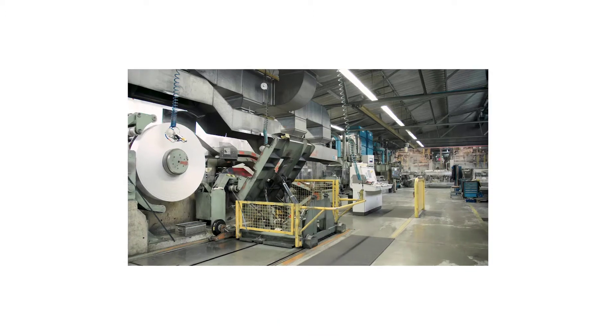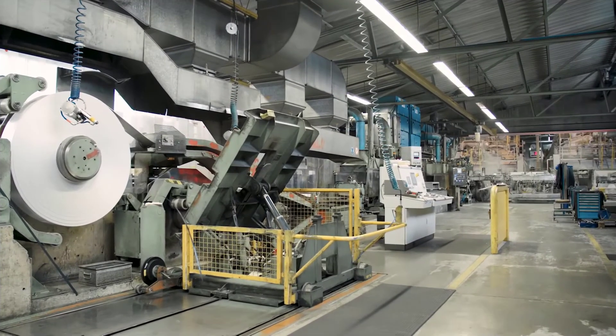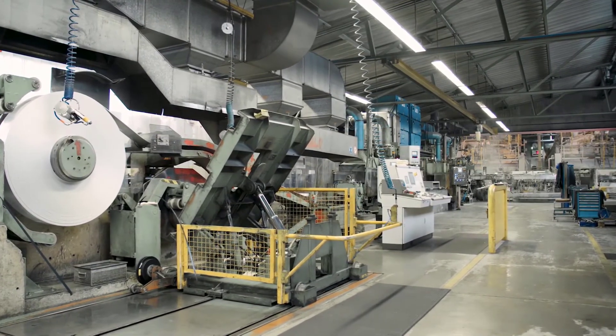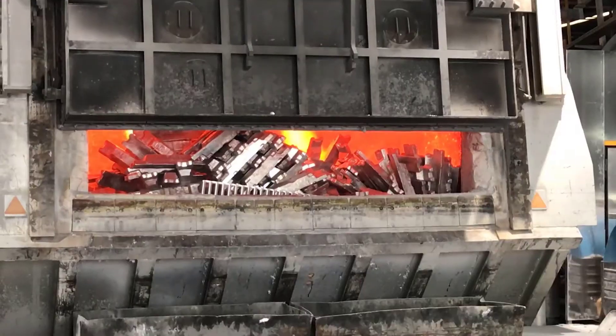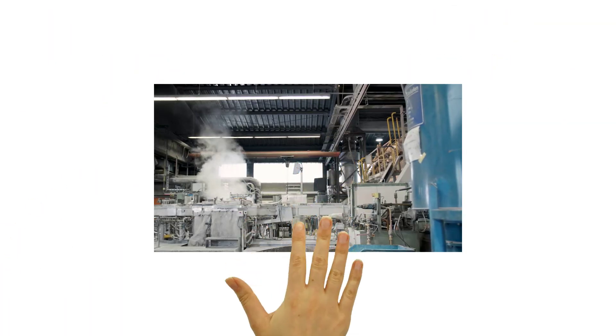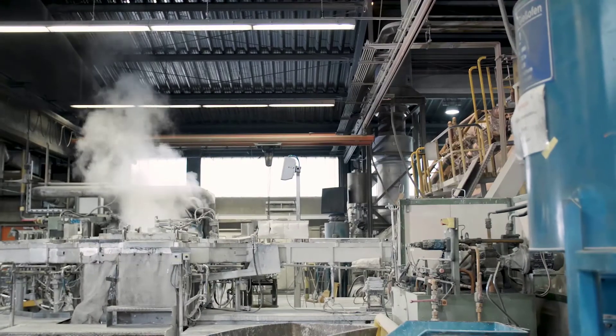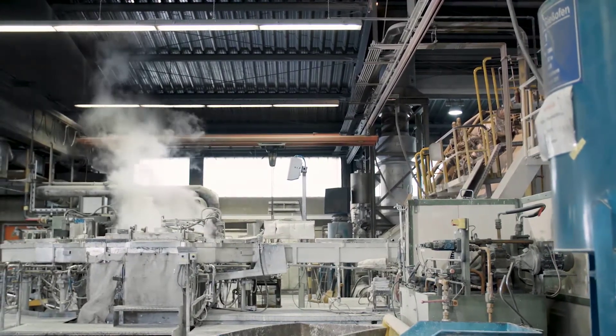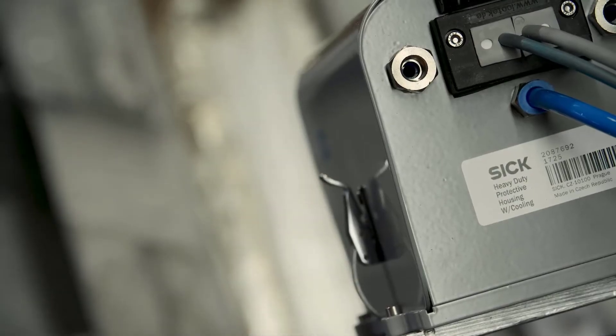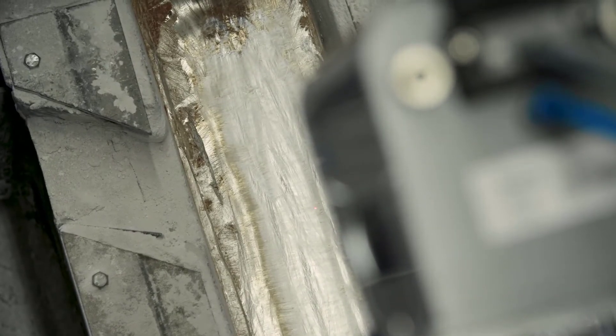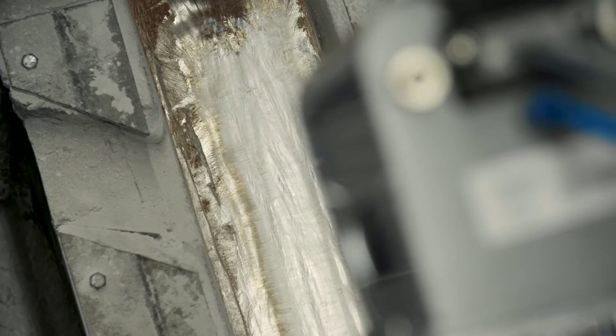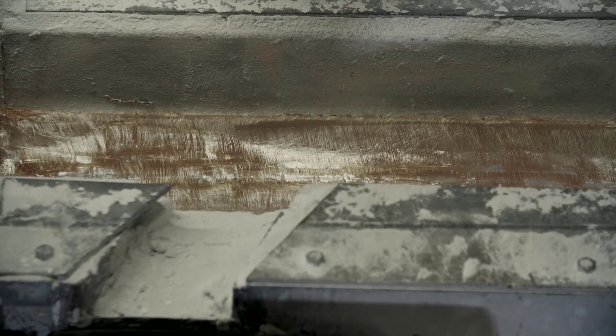When casting strips of aluminum from molten metal, it is essential to measure the level of the liquid aluminum in the feed channel and keep monitoring it at all times. The distance sensor measures the distance to the aluminum surface, which is at a temperature of around 660 degrees Celsius. If the aluminum surface is covered by an oxide, this process does not pose any issues.